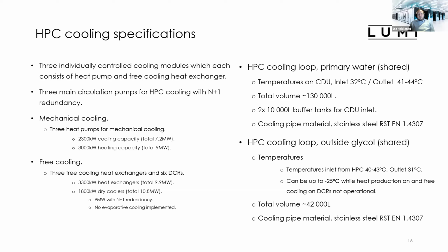The total volume of this cooling loop is 130,000 liters, and it includes two 10,000-liter buffer tanks for the inlet to the Lumi. These buffer tanks help us balance the variation from the cooling modules, so that we can keep a constant 32 Celsius to the Lumi cooling. All of our cooling pipe is made of stainless steel, so we don't have any plastic pipe in our data center.